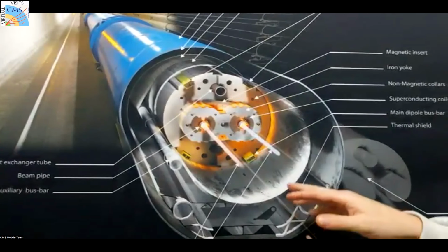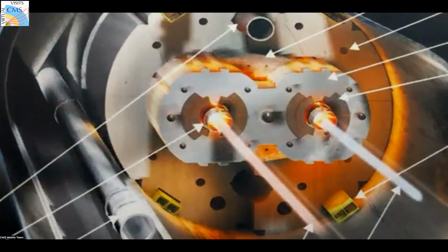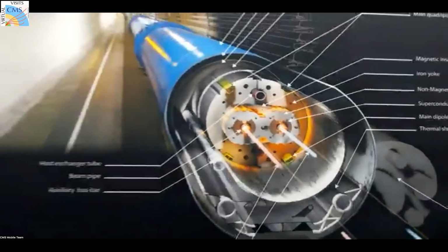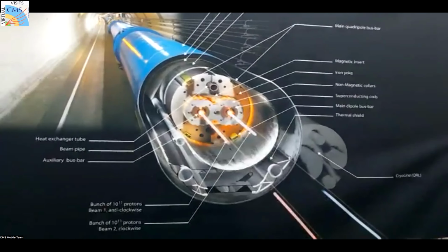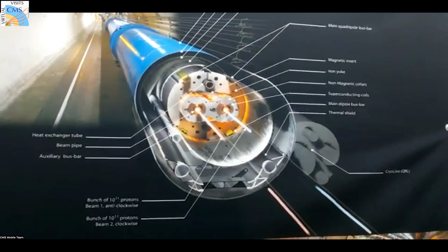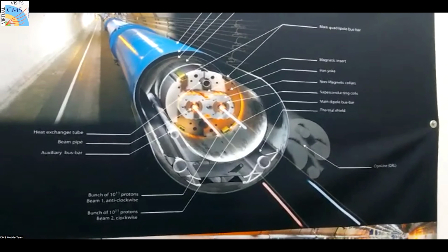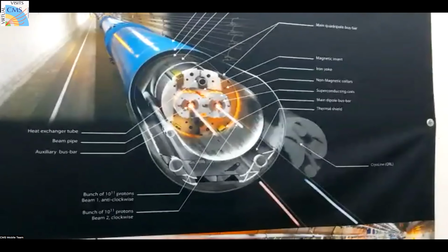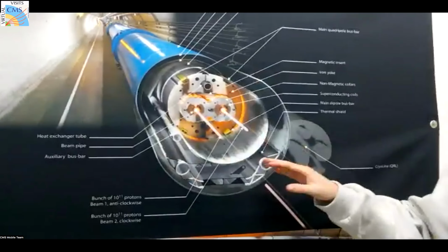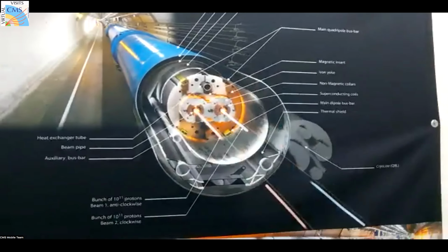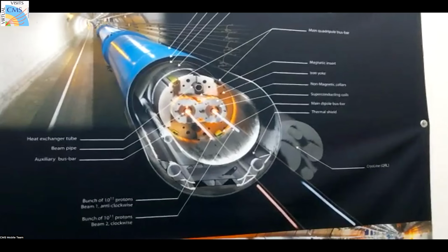It's because we have these superconducting magnets that are used to focus and steer the beam and keep it in the beam pipe. Since they're superconducting, they need to be at minus 270 degrees Celsius, which is only a degree or two above absolute zero. And we keep it that cold with liquid helium. So this whole thing is really almost like thermal insulation, you can imagine. It's to keep that as cold as possible to keep control of the beam.